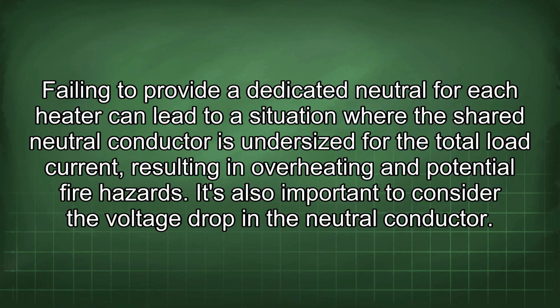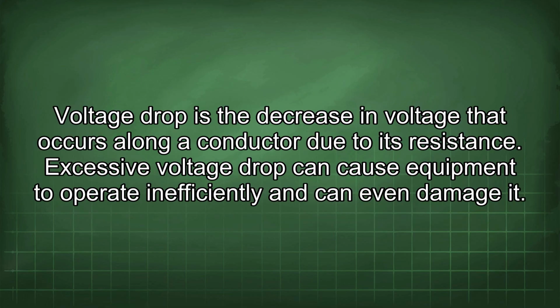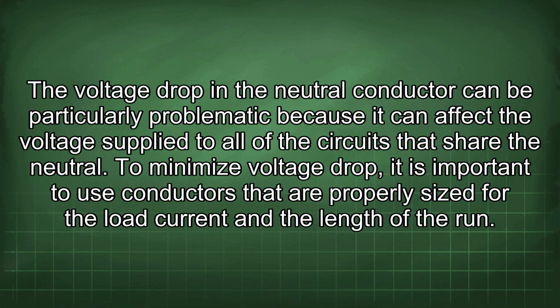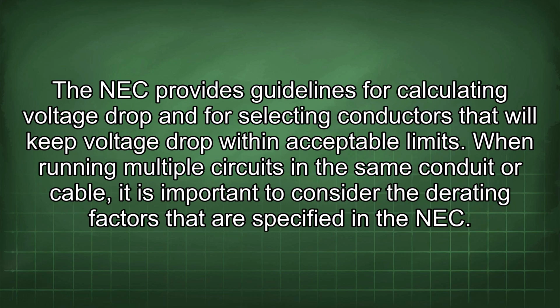It's also important to consider the voltage drop in the neutral conductor. Voltage drop is the decrease in voltage that occurs along a conductor due to its resistance. Excessive voltage drop can cause equipment to operate inefficiently and can even damage it. The voltage drop in the neutral conductor can be particularly problematic because it can affect the voltage supplied to all of the circuits that share the neutral. To minimize voltage drop, it is important to use conductors that are properly sized for the load current and the length of the run. The NEC provides guidelines for calculating voltage drop and for selecting conductors that will keep voltage drop within acceptable limits.